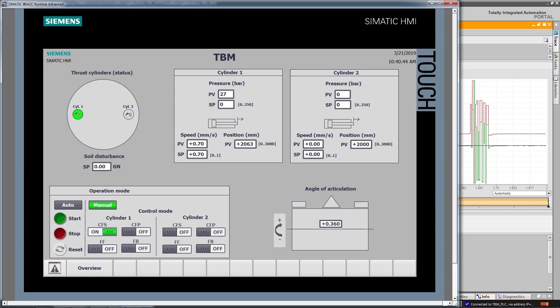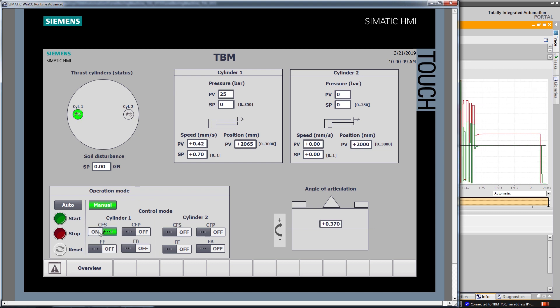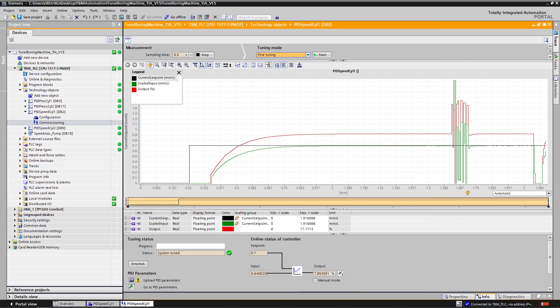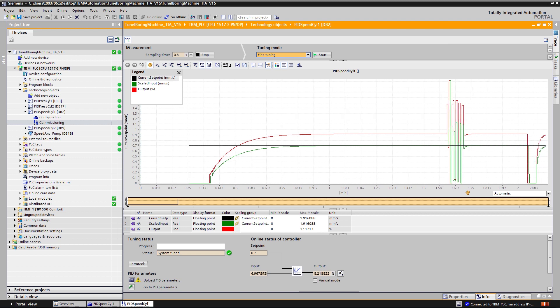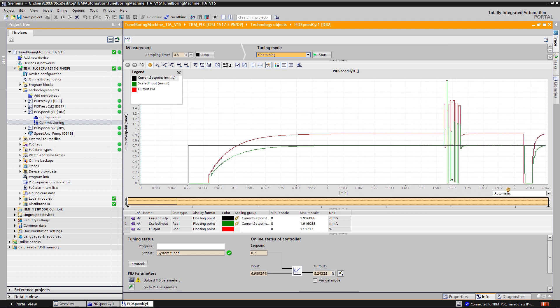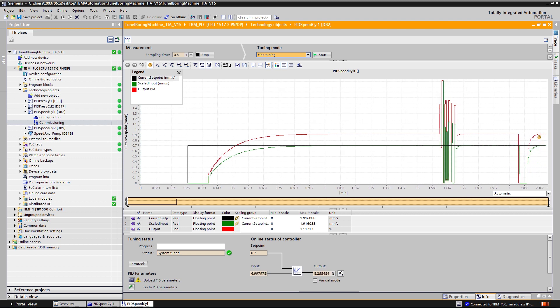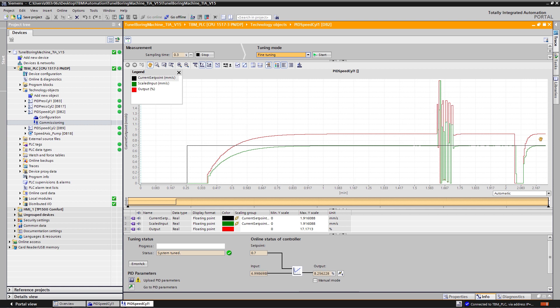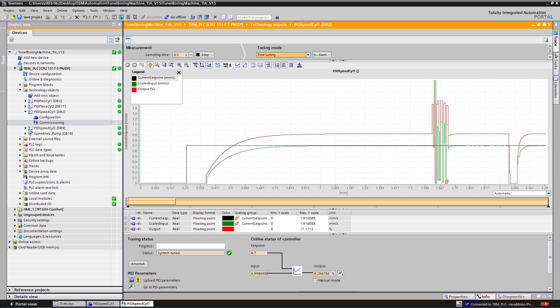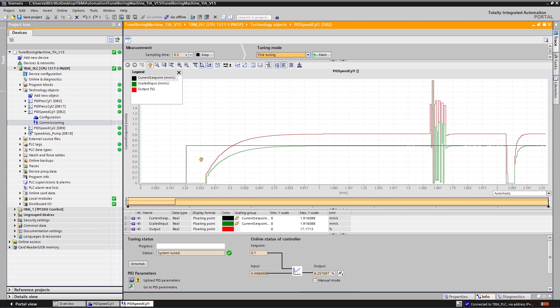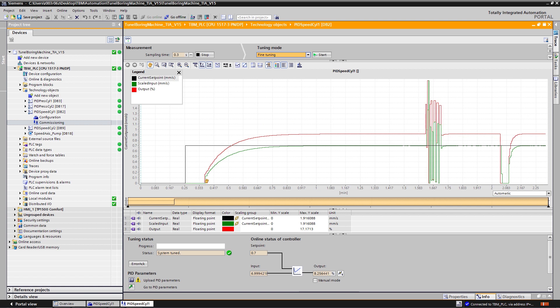On the HMI, I will deactivate and activate again the system response. And in the commissioning window on the right-hand side, we can see the new system response of my system, which is significantly much faster than the initial step response without optimized PI parameters.